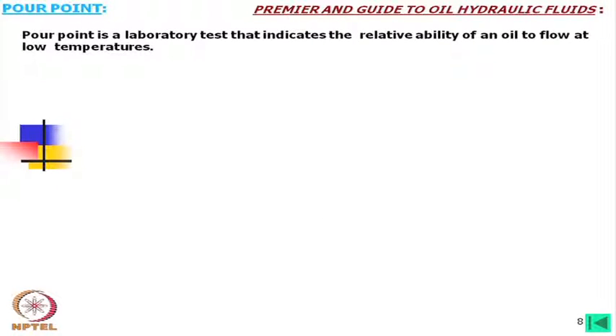Pour point is a laboratory test that indicates the relative ability of an oil to flow at low temperatures. It is determined by taking some oil in a beaker, cooling it down, and then trying to pour that oil into another container. The temperature at which the oil can no longer be poured is the pour point. This is important mainly where operations are held at very cold temperatures — for example, in European or northern countries. For those applications we need to take oil with a lower pour point.